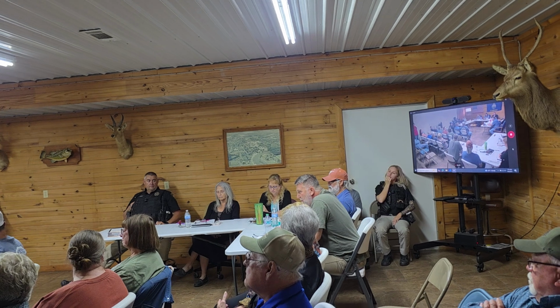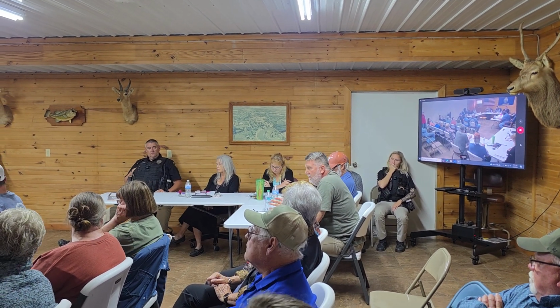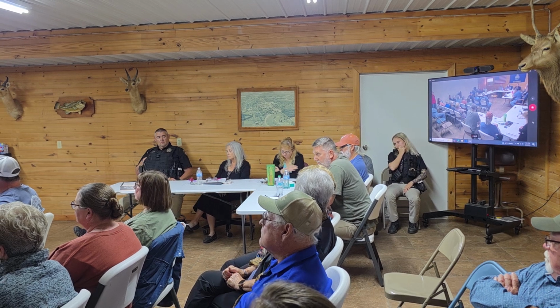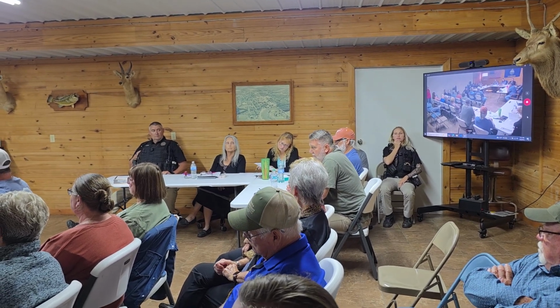Water plant supervisor. Today we had a couple of guys from McGuire Iron come out and do an inspection on our water tower, mainly the riser. The riser's the main line that takes water up to the bowl in the tower. The lifespan of those is typically 40 to 50 years. It was put in in 1975, so we're at 50. We took all the insulation off. He did an ultrasound on it, tapped around, scraped on it, and we found some leaks, and long story short, it needs to be replaced.